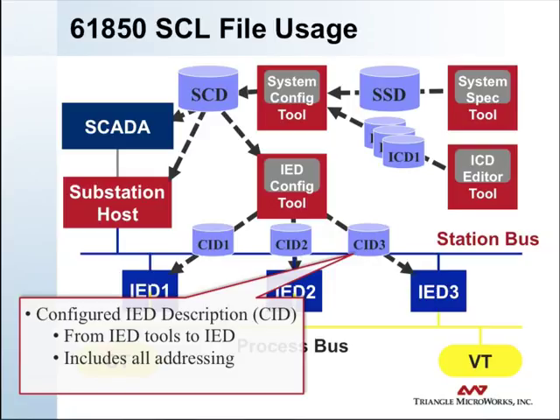They will take out the information from the full substation description that is specific to the IED, including all of the configuration parameters and addressing information, and put that in a smaller file which can be downloaded to the IED.